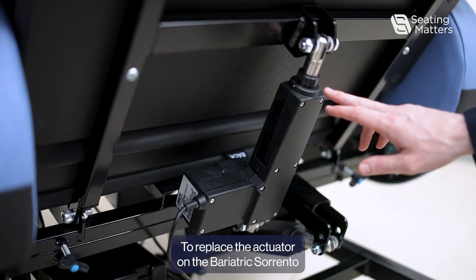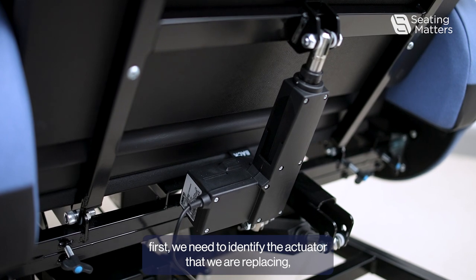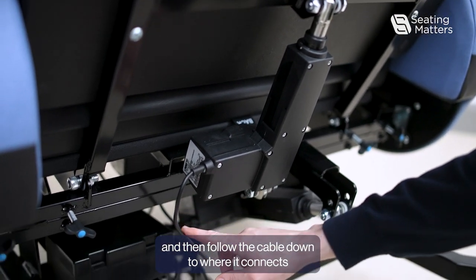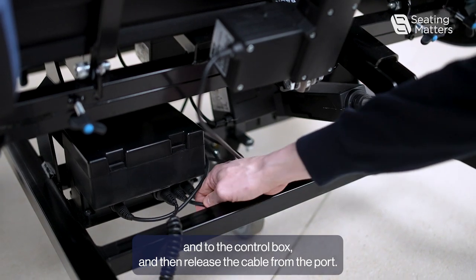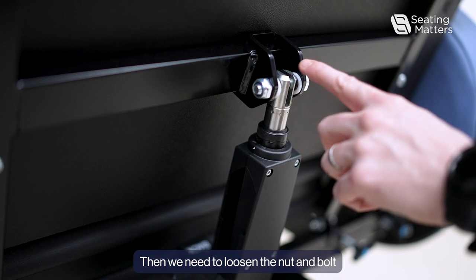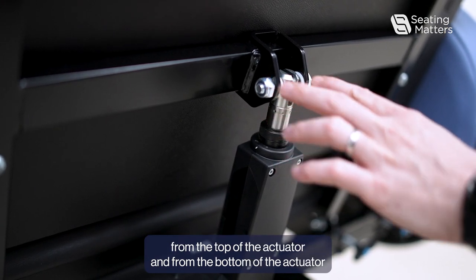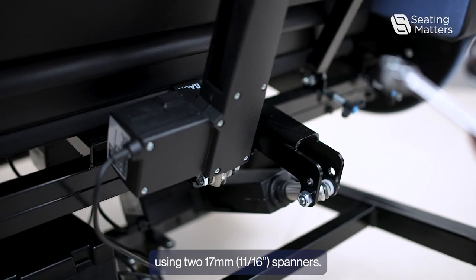To replace the actuator on the Bariatric Sorrento, first we need to identify the actuator that we are replacing, and then follow the cable down to where it connects into the control box and release the cable from the port. Then we need to loosen the nut and bolt from the top of the actuator and from the bottom of the actuator, using two 17mm spanners.